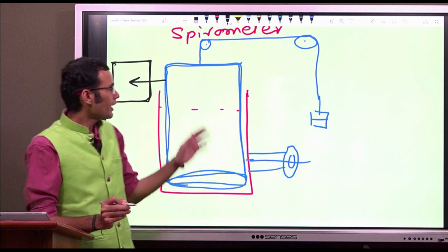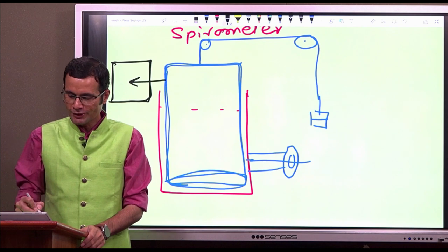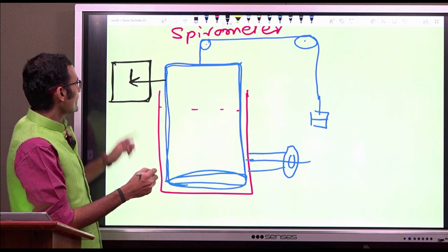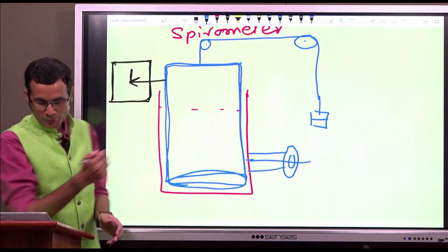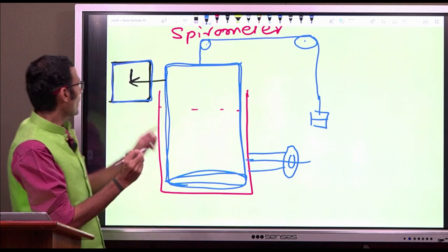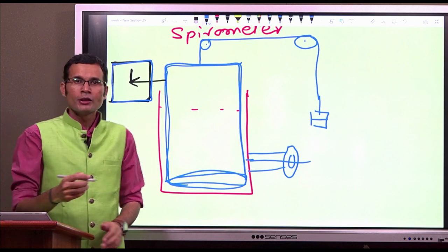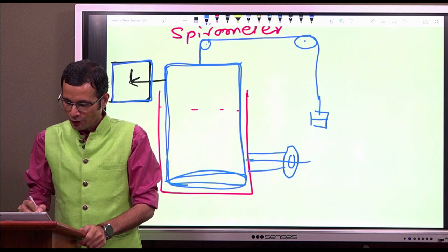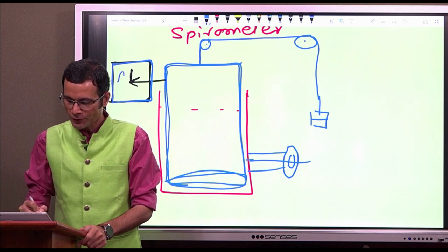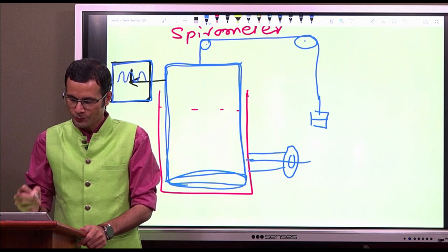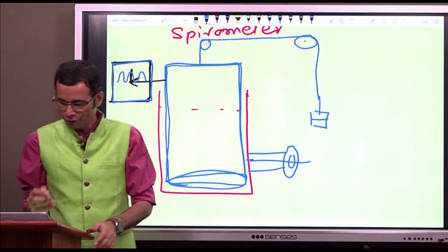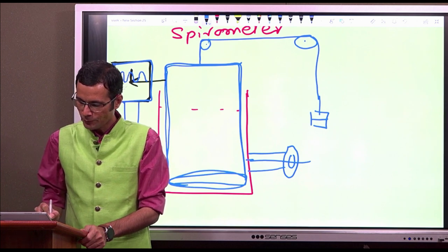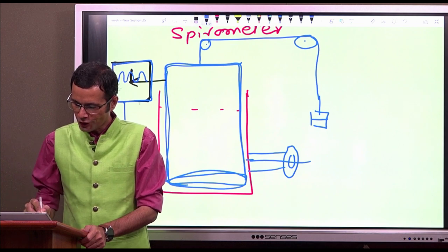We want to record those actual volumes by measuring the displacement of this inverted drum. There is a writing lever attached to this drum. This writing lever will move up and down to give us the idea of how much volume is being inhaled or exhaled. This movement is recorded on a revolving drum - inspiration the writing lever goes up, expiration it comes down - giving us a continuous spirogram with curves for inspiration and expiration.